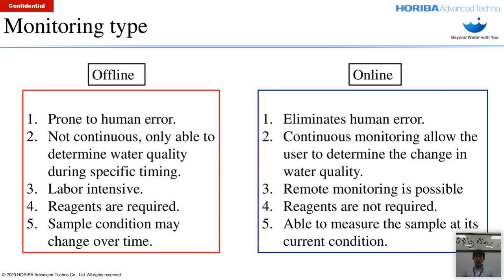Point number two, since offline monitoring is not continuous, it can only determine the quality of the water at a specific time when a sample was taken. On the other hand, online monitoring measures the water quality continuously, allowing the user to determine the water quality at any given time, giving the user a better picture and control over the entire process. For point number three, offline monitoring is labor intensive, while online monitoring is less labor intensive because everything can be done remotely from the water plant or office.